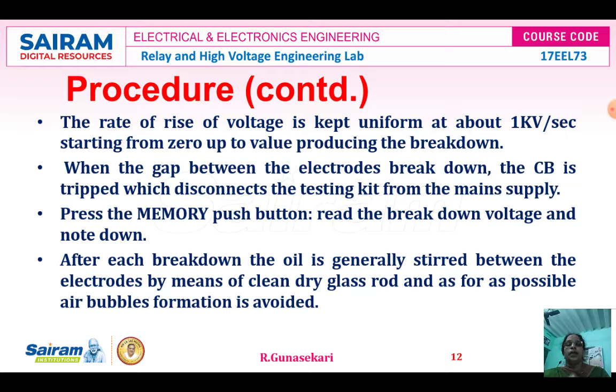When the gap between the electrodes breaks down in the form of electric arc, the circuit breaker is tripped, which disconnects the testing kit from the main supply. Now press the memory push button. Read the breakdown voltage which is shown in the high voltage voltmeter, that is charging voltage voltmeter, and note down the breakdown voltage in the tabular column. After each breakdown, the oil is generally stirred between the electrodes by means of a clean dry glass rod, and as far as possible the formation of air bubbles is avoided.